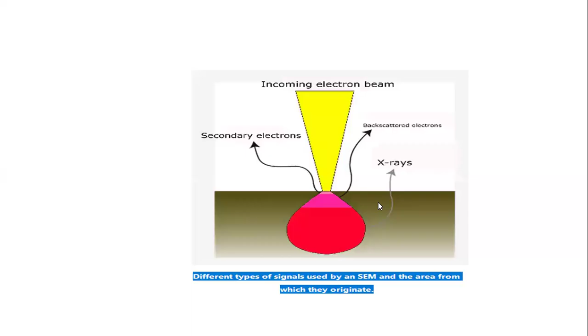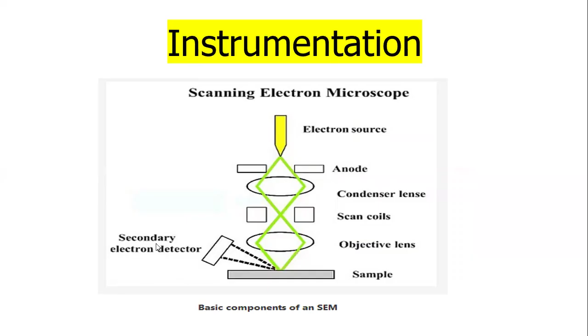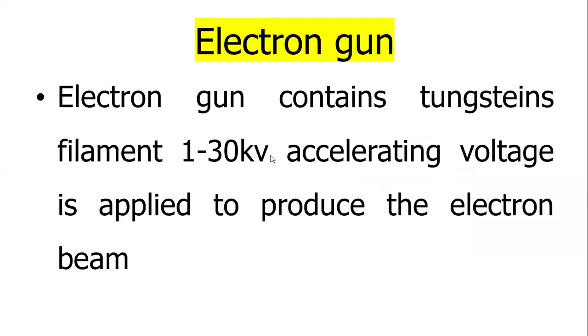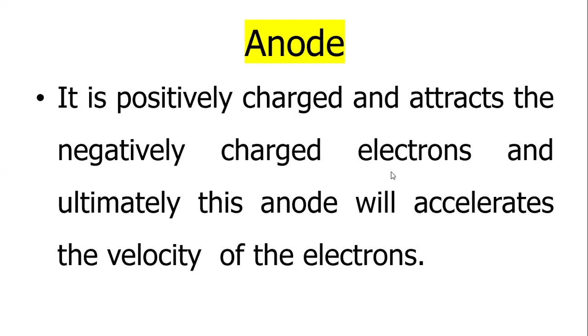Instrumentation of the scanning electron microscope: electron gun, anode, condenser, scan coils, objective lens, sample, and this is the secondary electron detector. The electron gun contains a tungsten filament. A 1 to 30 kilovolt accelerating voltage is applied to produce the electron beam. The anode is positively charged and attracts the negatively charged electrons, and ultimately this anode will accelerate the velocity of the electrons.